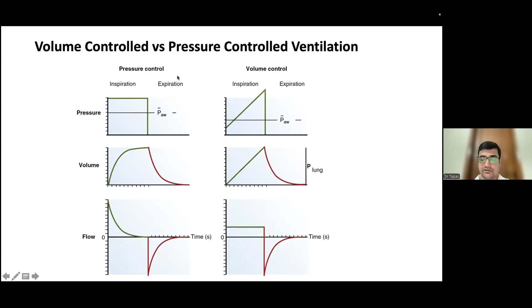So if you focus on this pressure-time curve, as we know, the area under the pressure-time curve indicates the mean airway pressure. Okay. So if you see the area of this pressure-time curve, there's a mean airway pressure. So you can make out that the mean airway pressure in pressure control ventilation is higher as compared to that of volume control ventilation. So this you have to remember, the mean airway pressure in pressure control ventilation is higher as compared to the volume control ventilation. And in volume control ventilation, the ventilated breaths are actually backloaded as compared to front loaded in case of pressure control ventilation.